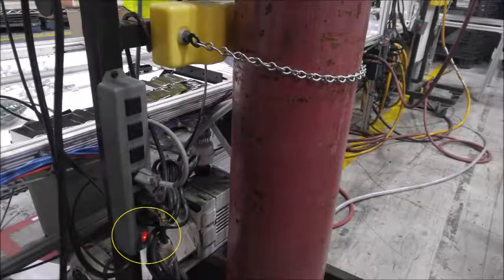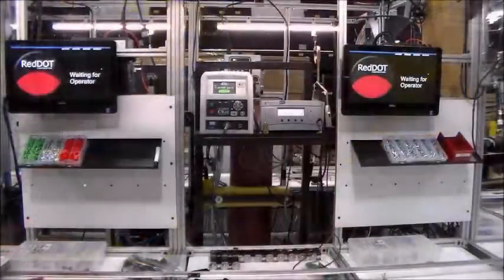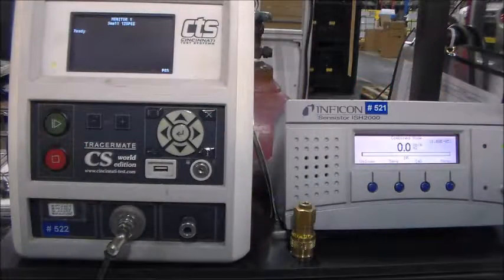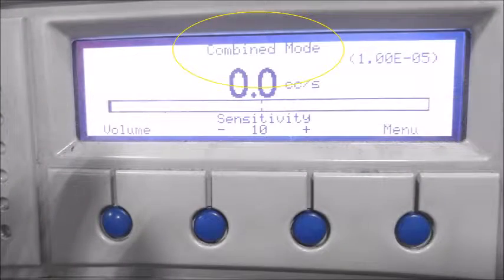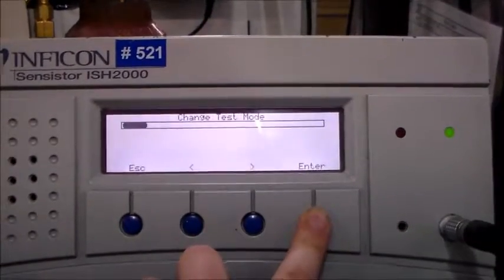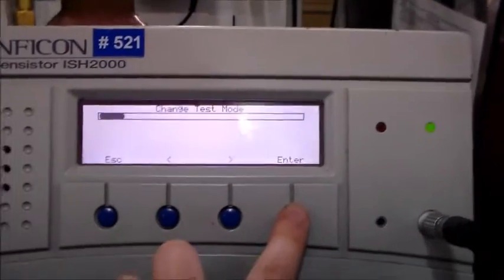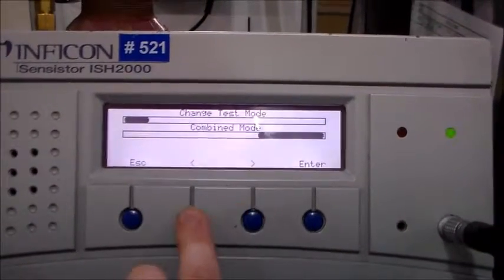So first, let's go over how to set up the hydrogen sniffer. Turn on the power to the system using the power strip attached to the back. Allow the machine to warm up for 2 minutes. Verify the following settings are correct for the ISH2000. Make sure the detection mode is set to combined. If it is not, press the menu button, then press Change Test Mode. Scroll until you reach combined and set the mode.